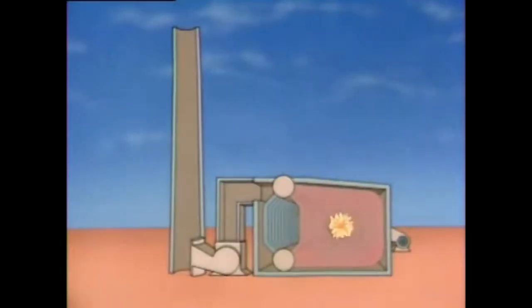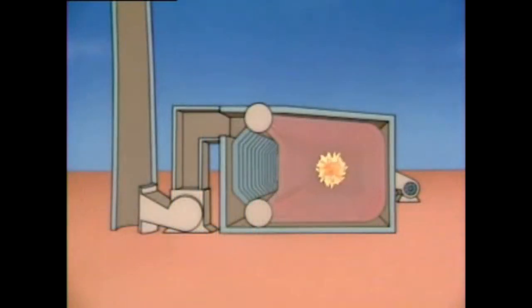The airflow into a boiler provides oxygen for combustion. Gases produced during combustion flow out of the boiler and are discharged from the stack. The flow of air and other gases through a boiler is referred to as draft. The components typically used to provide draft are fans. There are two basic categories of draft fans: forced draft fans and induced draft fans. As their name implies, forced draft fans force air into the boiler.